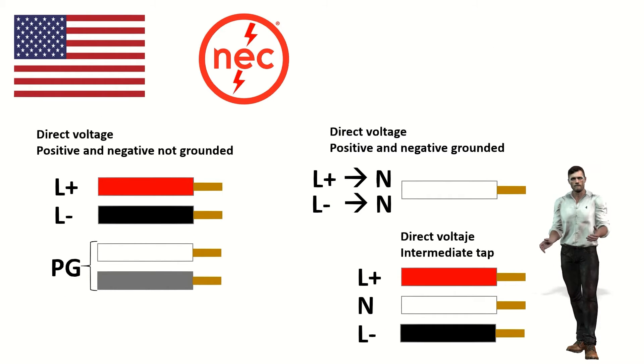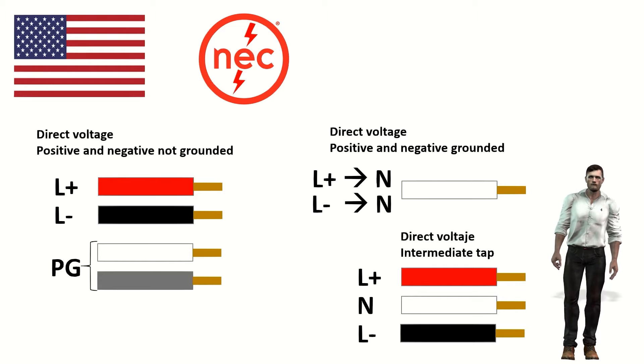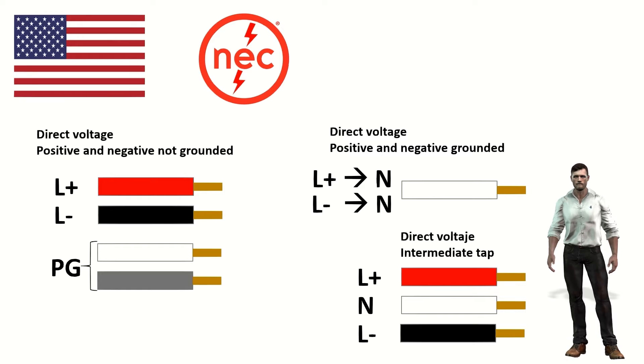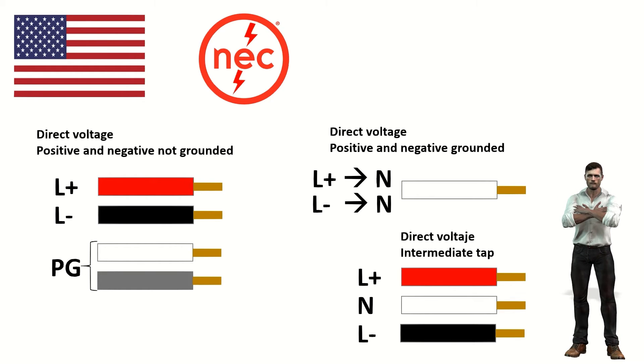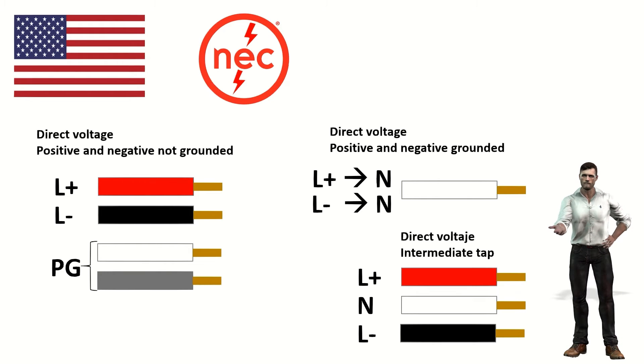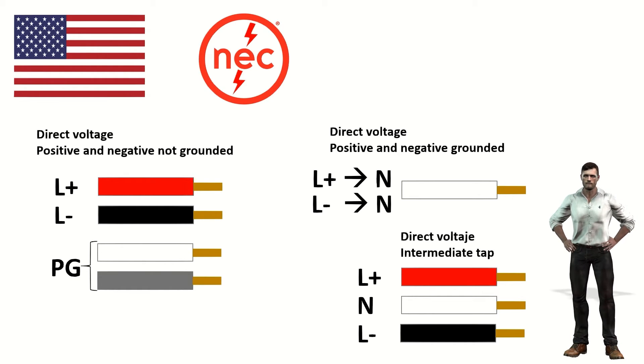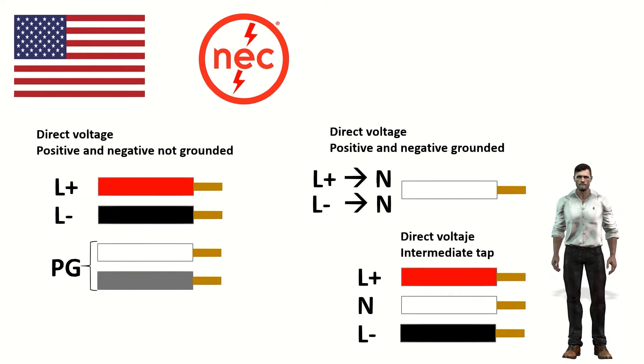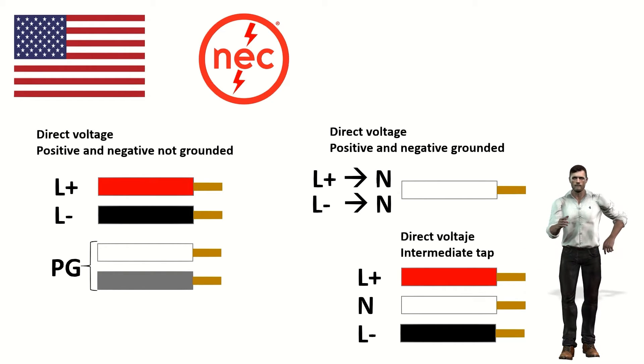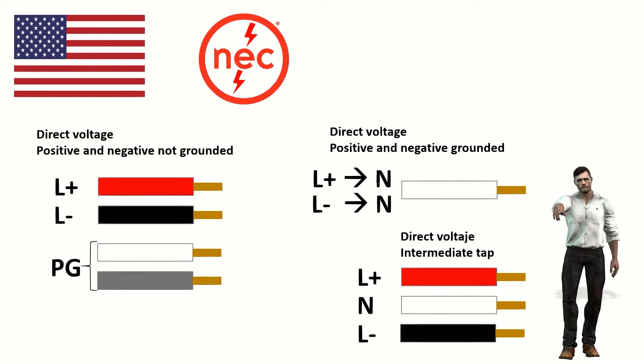For systems that work with DC voltages, for example in photovoltaic installations, battery systems, etc., we have red for the ungrounded positive (L+), black for ungrounded negative (L-), and white or gray for protective earth (PG). In case the positive or negative is grounded, then the color white should be used instead of red or black, and it would be labeled as N. And if it is a system with an intermediate tap, the color white will be used for the tap, labeled with the letter N.